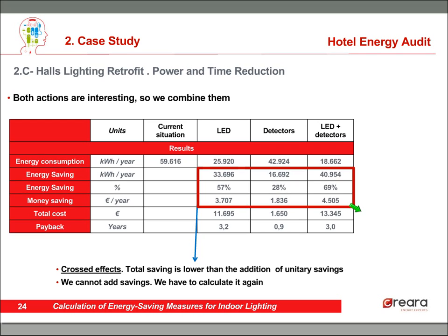So the payback of LEDs is 3.2 years. For the detectors, as we said, less than a year, 0.9 years. With the two actions combined, we have a total cost of 13,000 euros and a money saving of 4,505 euros. So the payback is 3 years.